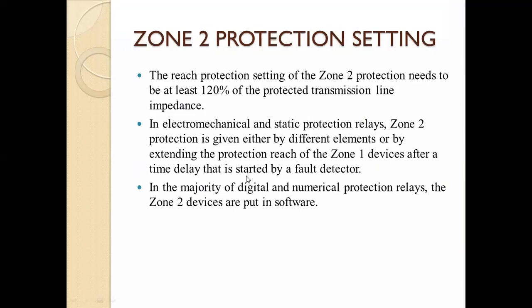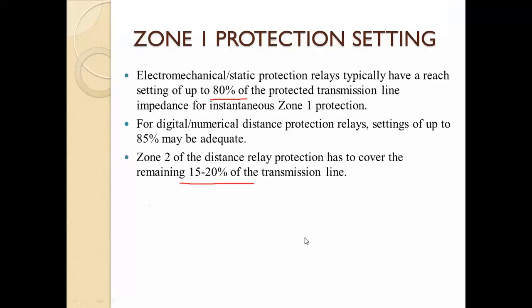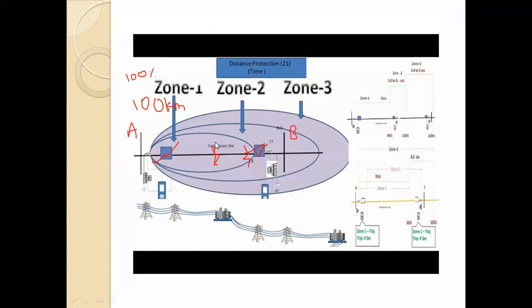Okay. Now here what happens? For zone 1, your relays are operating instantaneously. For zone 2, operating time is increased, suppose 0.2 to 0.4 seconds. And for zone 3, operating time is above 0.4 or 0.5 seconds.